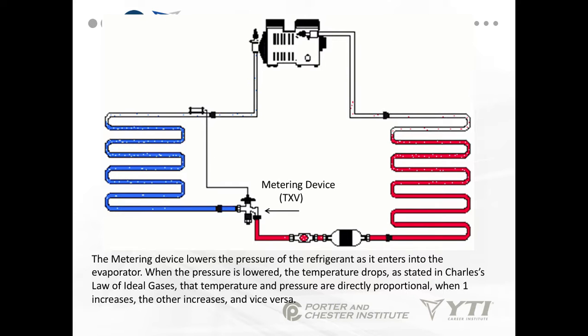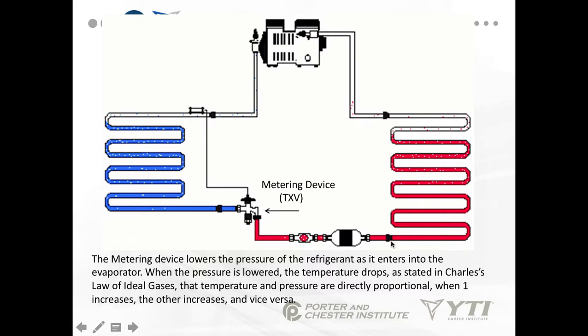The metering device is designed to lower the pressure of the refrigerant as it enters the evaporator. Coming out of the condenser, you have high-pressure liquid. The metering device acts like a finger over the end of a garden hose — it takes this high-pressure liquid and allows a little bit at a time to spray into the evaporator. That means the pressure in the evaporator is much lower than the pressure in the liquid line behind it.